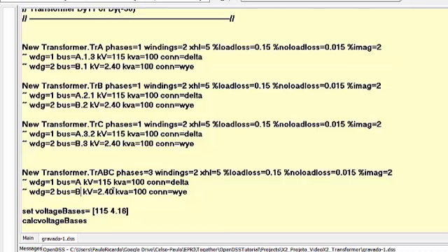We need to update the rated voltage of the secondary side to the line-to-line voltage of 4.16 kV, and the rated power of the transformer must be multiplied by 3 in order to have the correct values for the series and shunt resistance and reactances calculated based on the parameters XHL, load loss, no load loss, and %imag when they are converted to ohms internally in OpenDSS.